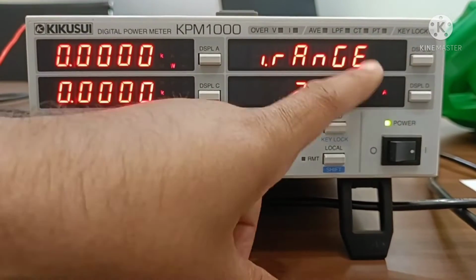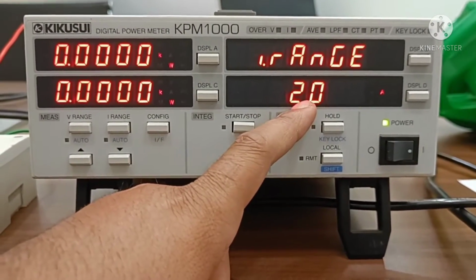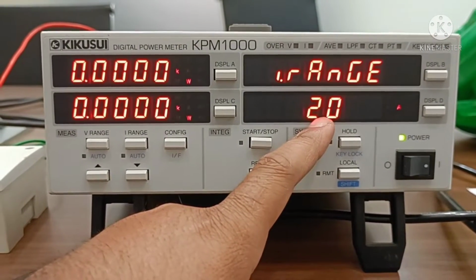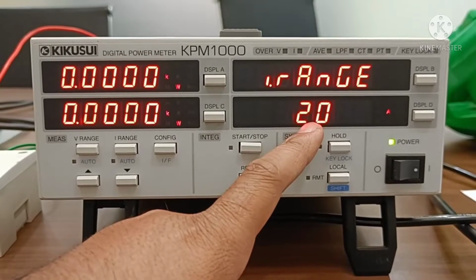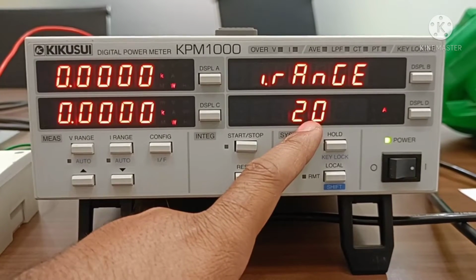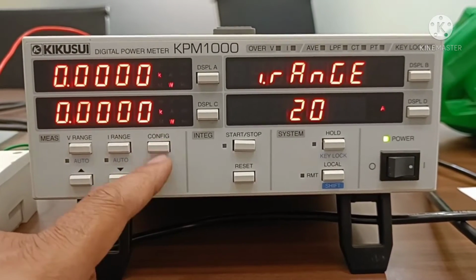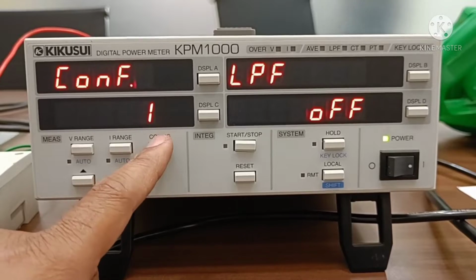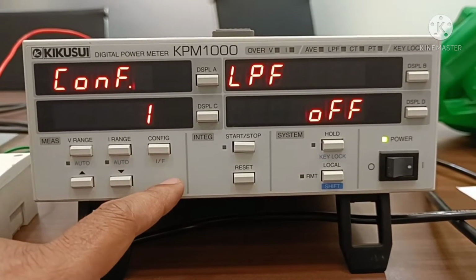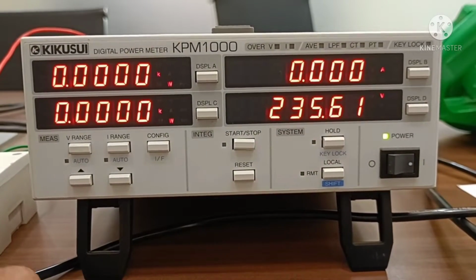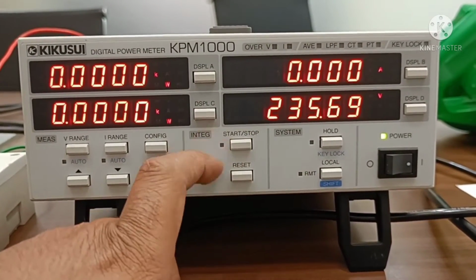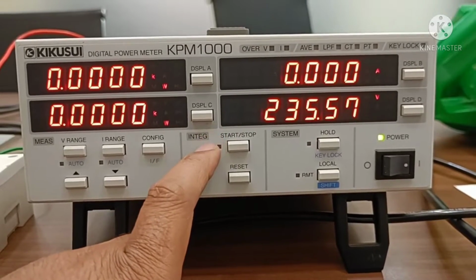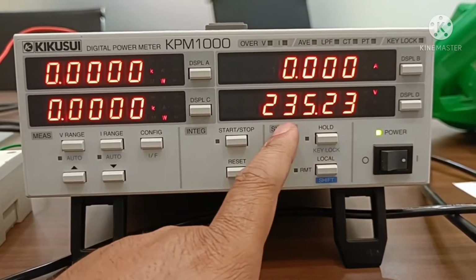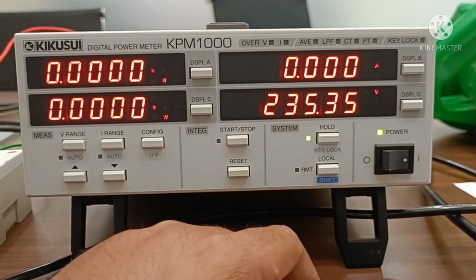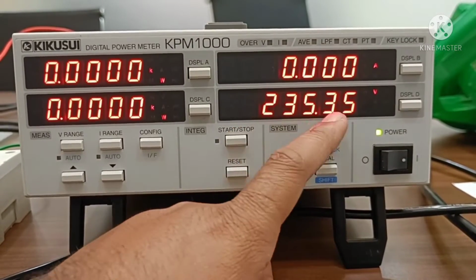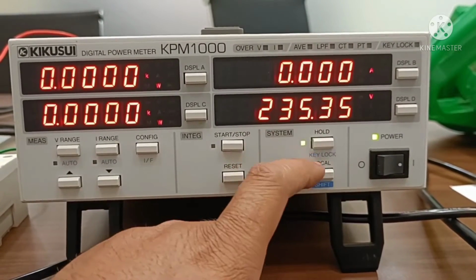For high currents, the maximum current is 20 amperes. This can be increased by using a current transformer, so what current you require, accordingly you can change the CT probe. This is a configuration related to instruments, like RS-232 and the low pass filter, which you can read about in the user manual. This is the integration part: once it starts, it calculates the power consumption depending on the load. This is the hold setting: if you want to hold the reading, it will hold, so the readings will not fluctuate. This setting is provided.